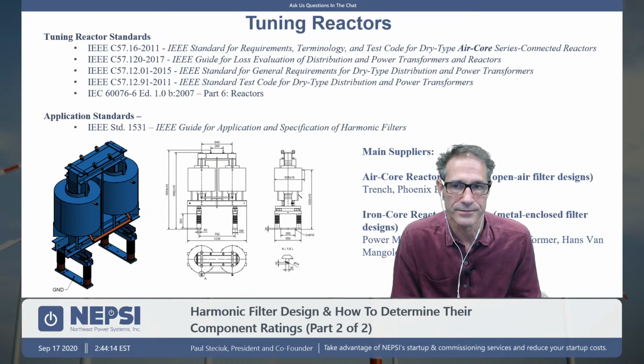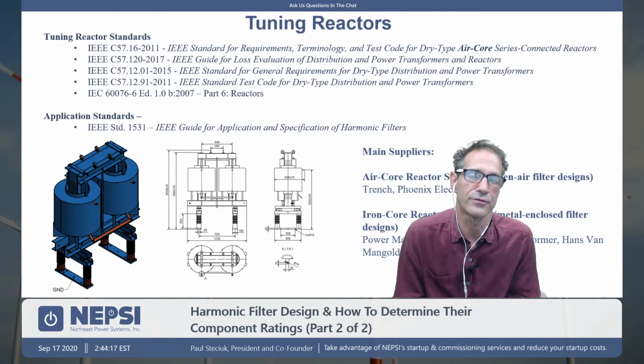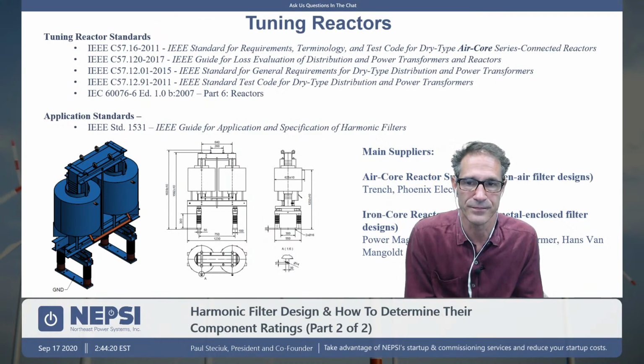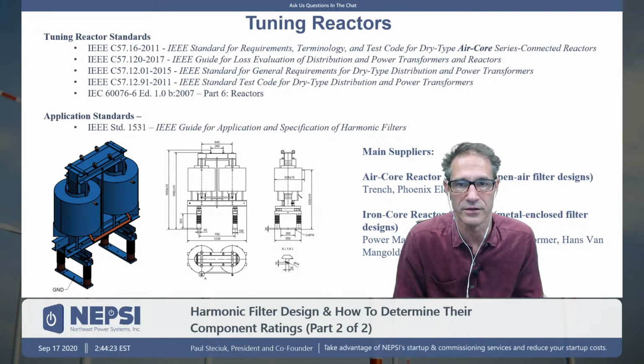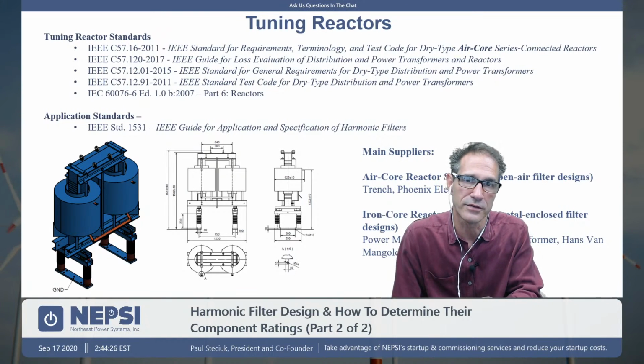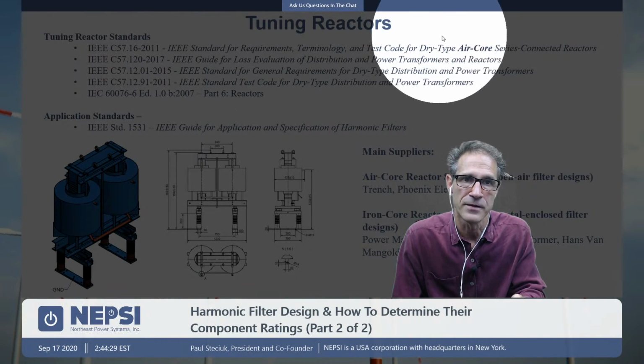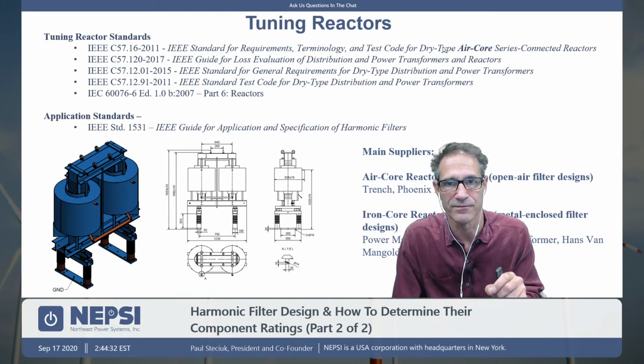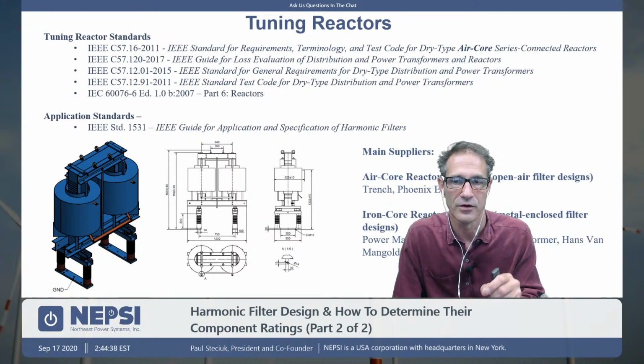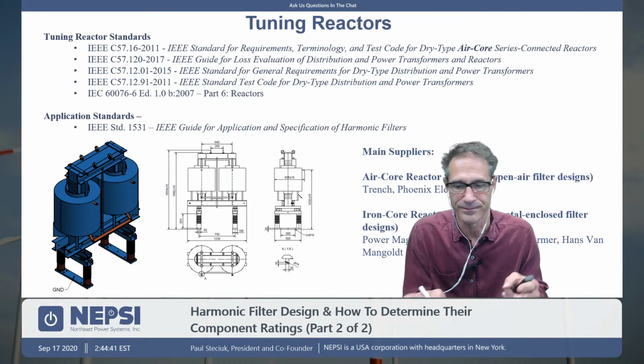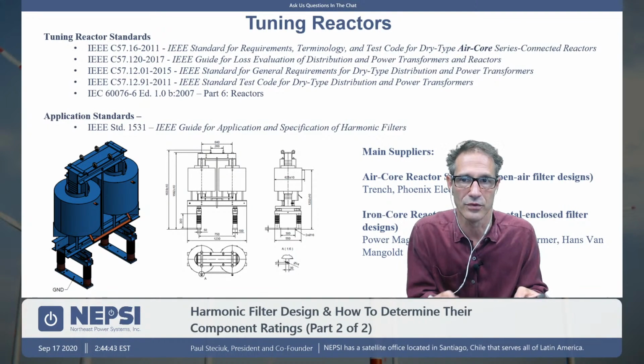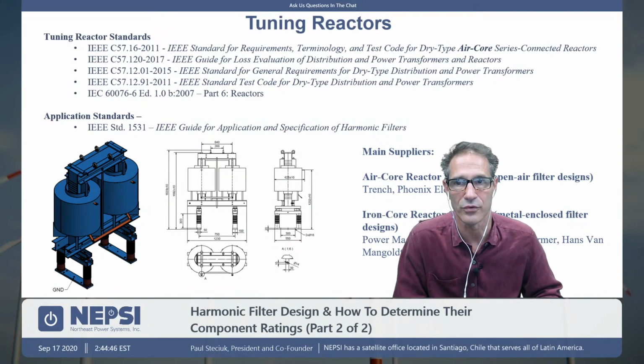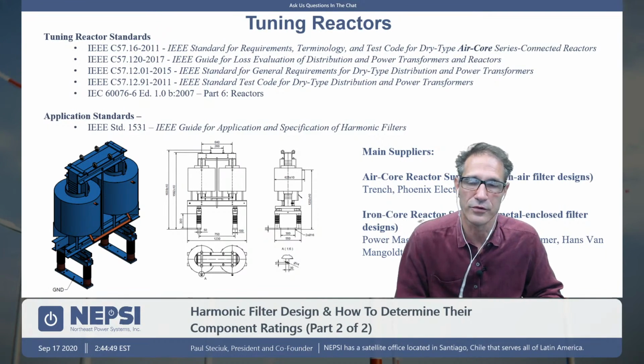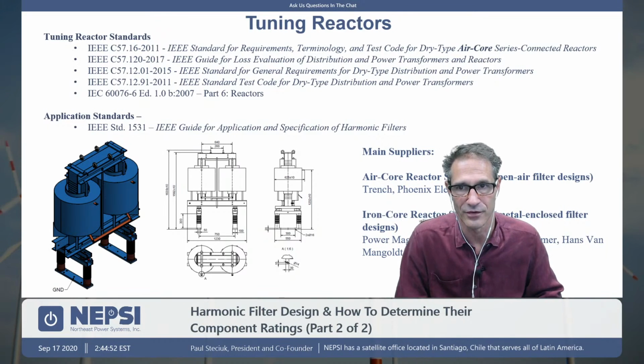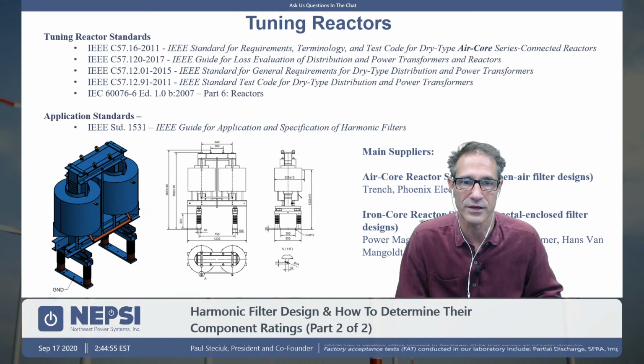By and large, metal enclosed systems use iron core reactors. Open air systems use air core reactors. So that's our first key differentiator. We'll talk about that. But these are the standards that cover iron core reactors. And there's really not a standard that specifically addresses all the issues and tests required for harmonic filter reactors. Typically, it's pieces of various standards that are utilized to define the tests required for iron core reactors. But if there's anything that's critical in a harmonic filter, it is the iron core reactor. I can't overstress that.